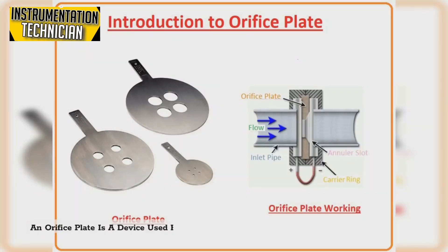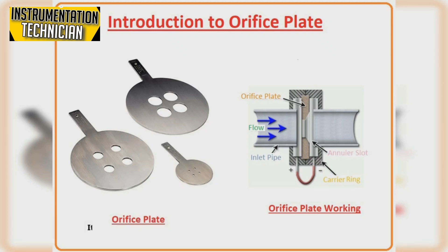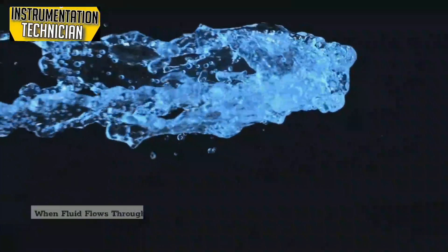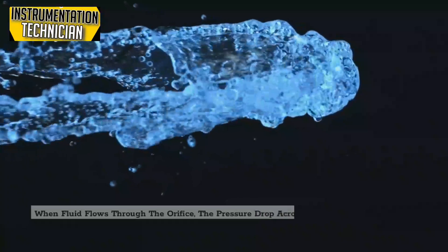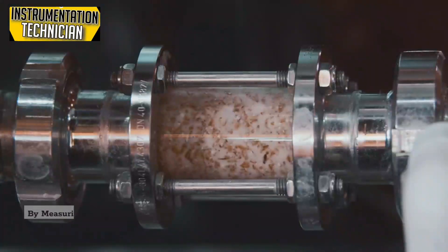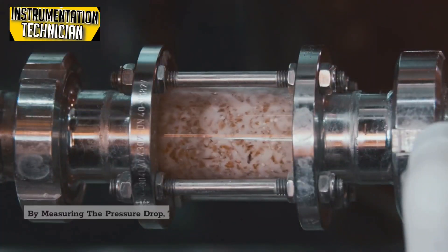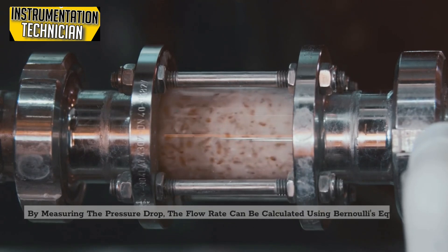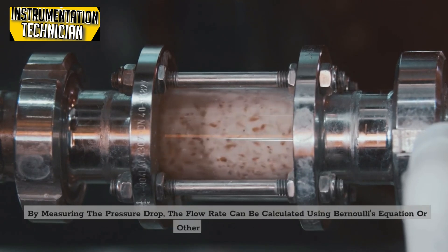An orifice plate is a device used for measuring the rate of fluid flow, typically in a pipeline. It consists of a thin plate with a hole, the orifice, in the center. When fluid flows through the orifice, the pressure drop across the plate is proportional to the flow rate. By measuring the pressure drop, the flow rate can be calculated using Bernoulli's equation or other flow equations.